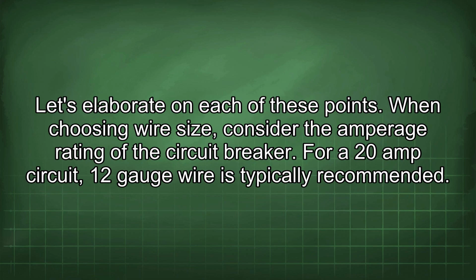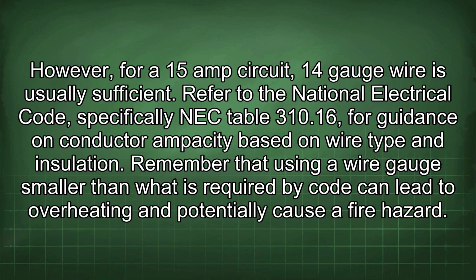When choosing wire size, consider the amperage rating of the circuit breaker. For a 20 amp circuit, 12 gauge wire is typically recommended. However, for a 15 amp circuit, 14 gauge wire is usually sufficient. Refer to the National Electrical Code, specifically NEC Table 310.16, for guidance on conductor ampacity based on wire type and insulation. Remember that using a wire gauge smaller than what is required by code can lead to overheating and potentially cause a fire hazard.